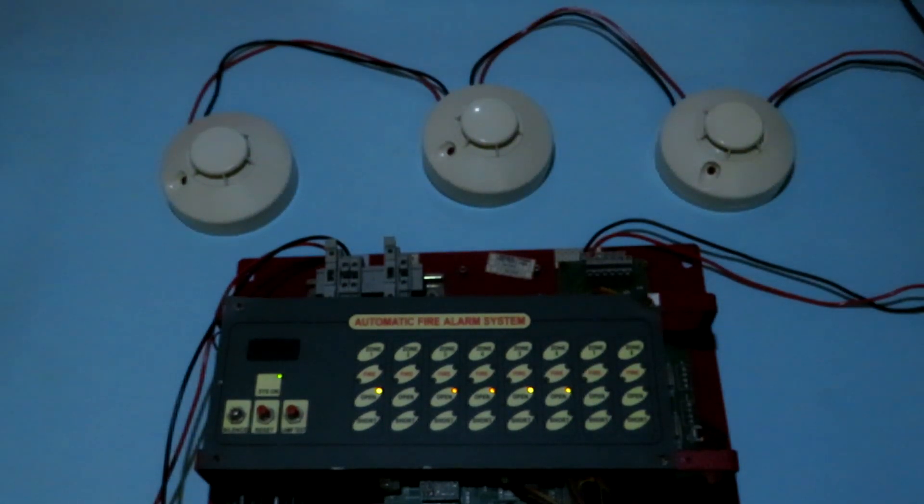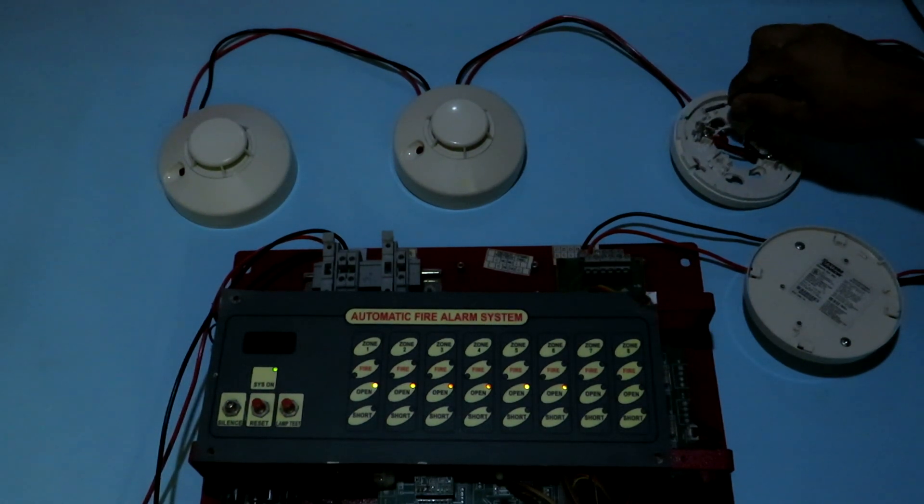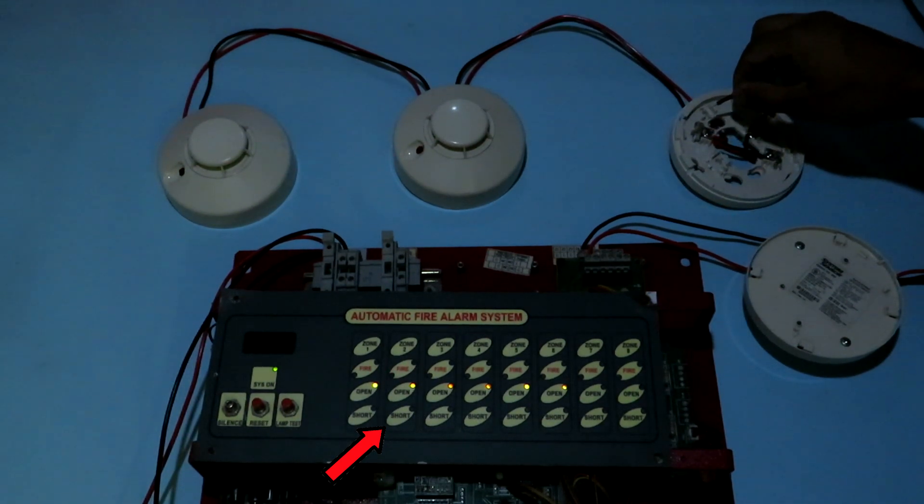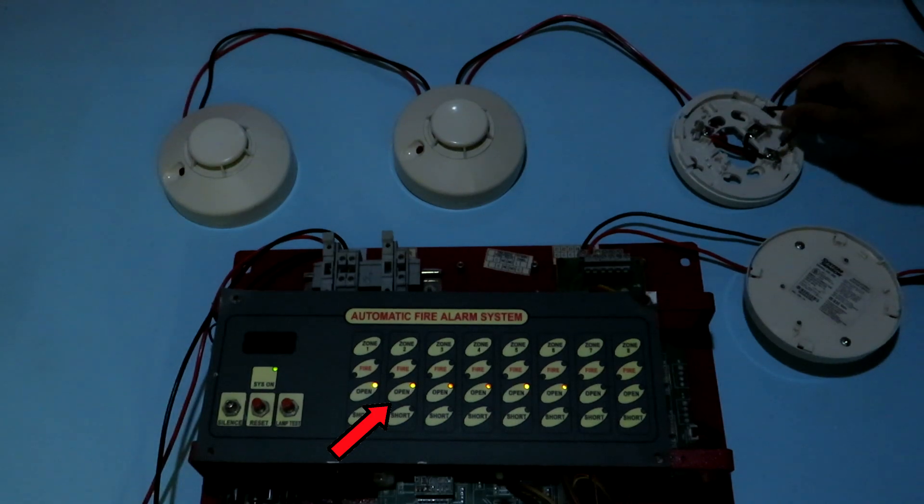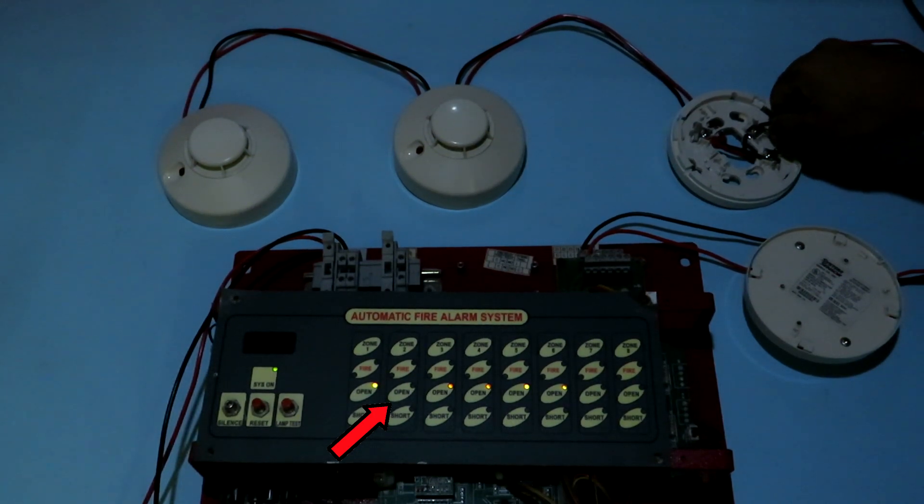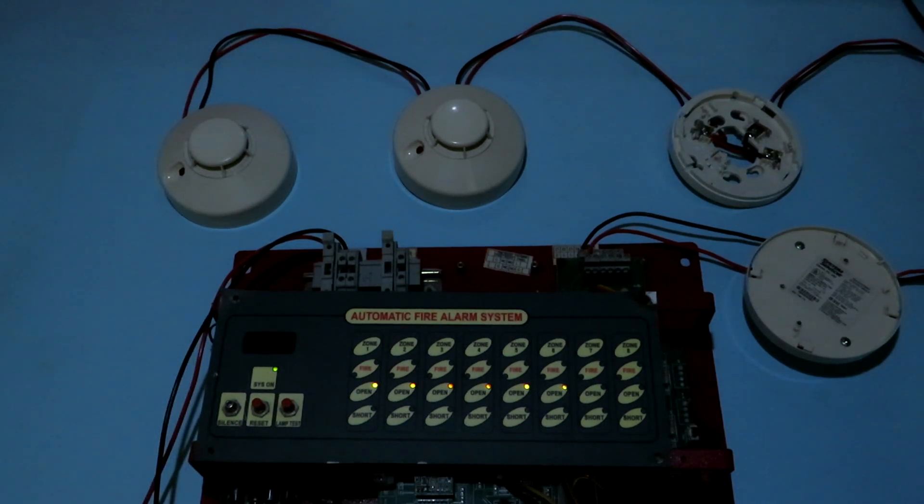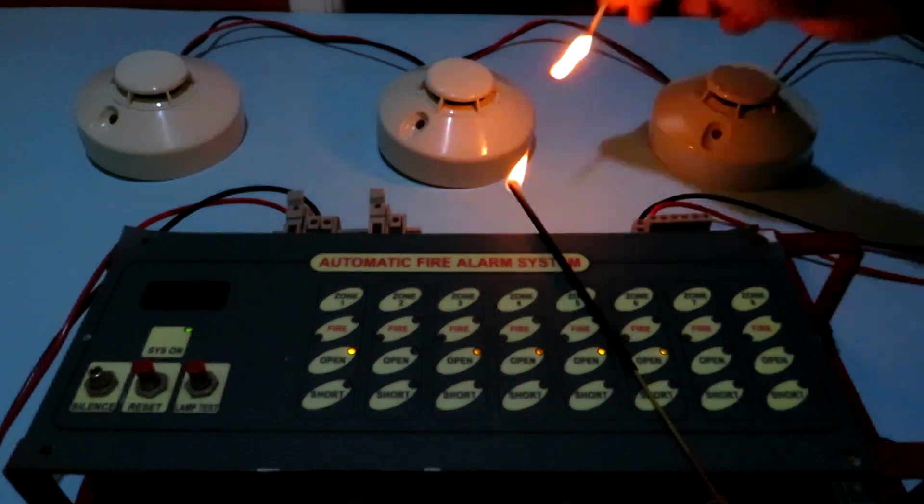Now if I attempt to create a dead short condition between the positive and negative terminal the short circuit LED for zone two will switch on therefore indicating that the line has been shorted somewhere. Here if I short the negative in and out terminals you can see that the open circuit indication for zone two goes off because that's what the smoke detector unit essentially does. As I explained to you earlier that the negative in and negative out terminals inside the smoke detector unit are shorted.